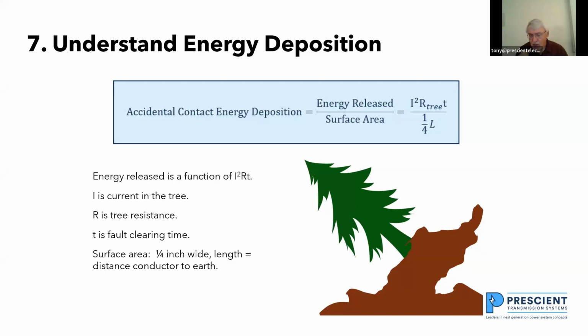But when I'm looking at ignition, typically I get an arc associated with current flowing through a tree, and that's going to be in a relatively small area, about a quarter inch. So we've done these calculations with I squared R of the tree, and R of the tree is a function of the length of the tree, where we use 2,000 ohms per foot. But the surface area is a quarter inch times the length of the tree. So if the tree is 40 feet long, it's only a quarter inch wide. The surface area is not the whole surface area of the tree, it's just a conduction area through the bark of the tree.